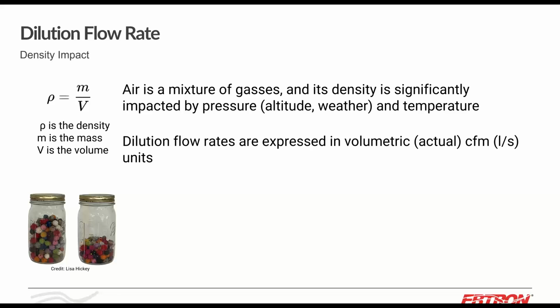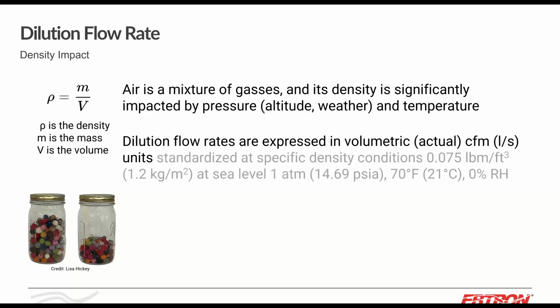The flow rates that are in 62.1, 62.2, 170, the IMC, the UMC are all expressed in actual flow rates, but they're tied to standard conditions. They're standardized, and this is the most common standard condition there is: 70 degrees at sea level, at 0% RH, dry air.